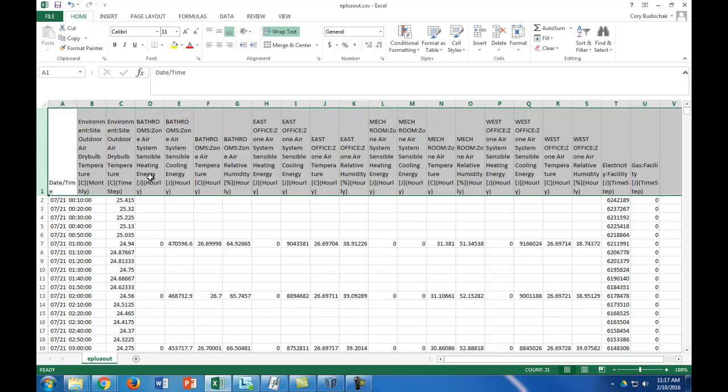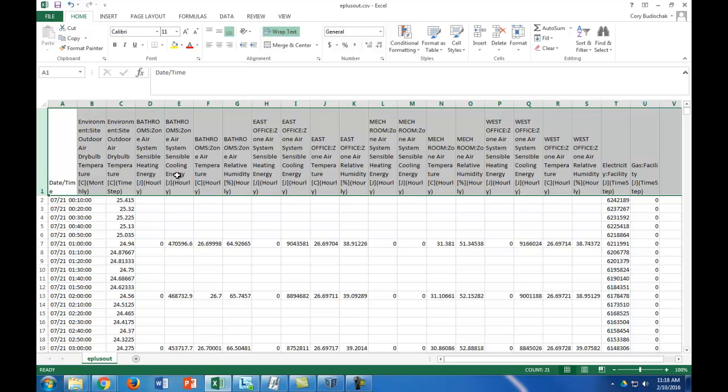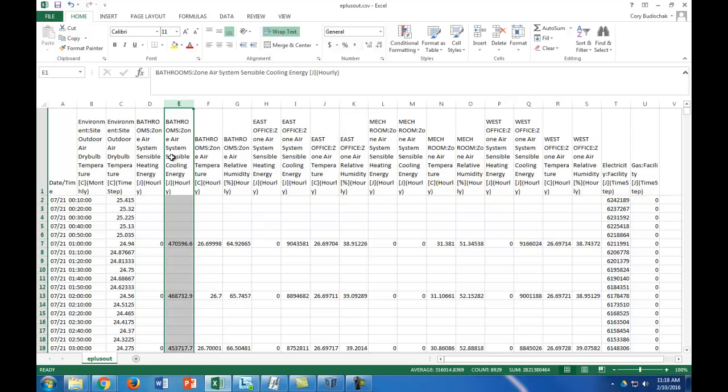This is the bathrooms zone air sensible heating in joules and then the cooling energy in joules for the bathrooms as well. It also gives the zone air temperature and relative humidity. To get the total cooling or heating load, you'd have to sum all of the cooling energy columns for each thermal zone. That's the way you would do that.